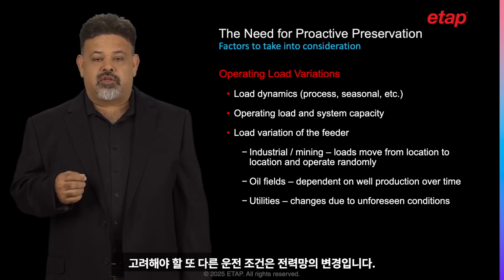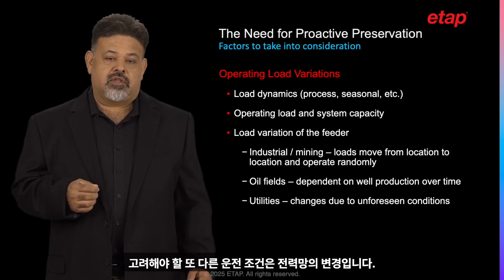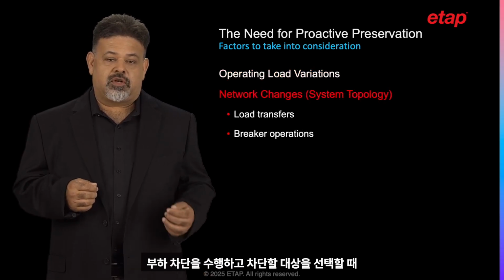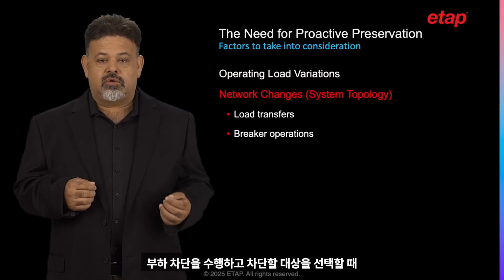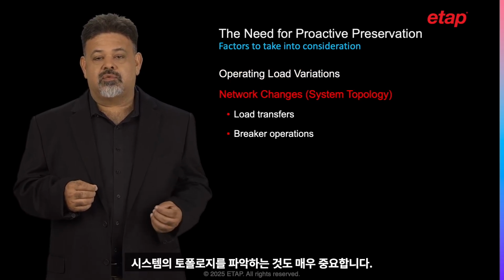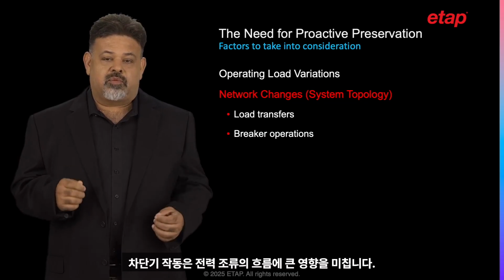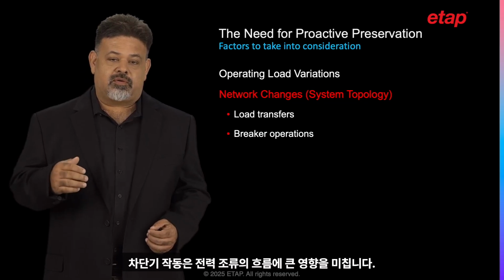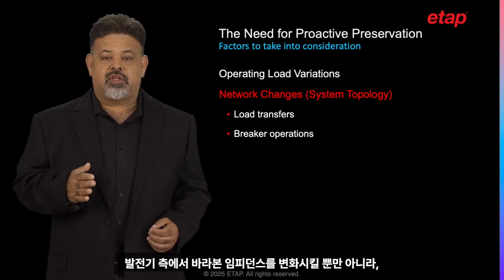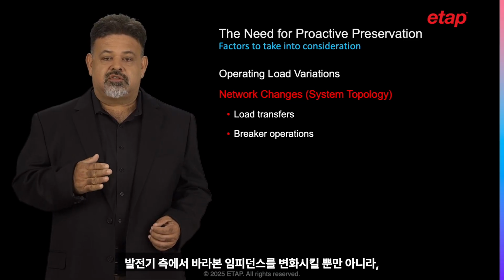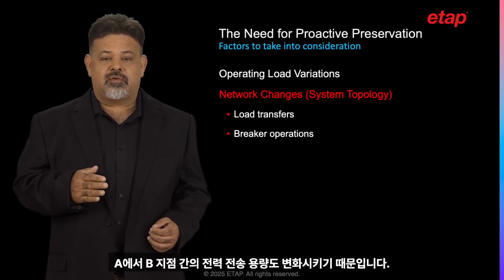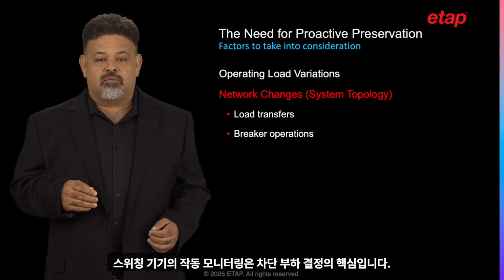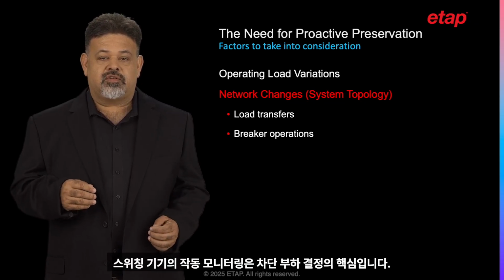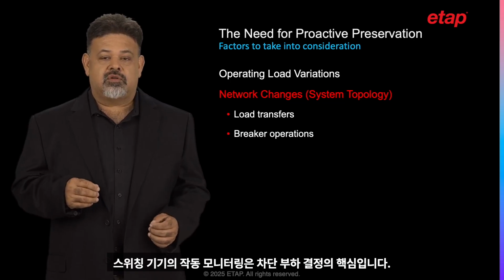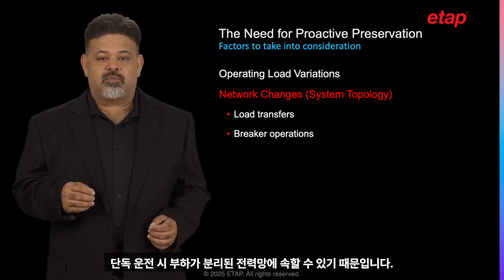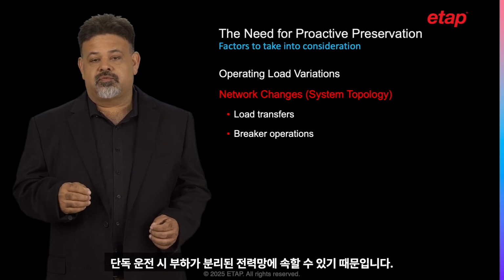Other system operating conditions to consider are network changes. The system topology is also important to know when performing load shedding and selecting which loads to drop. Breaker operations greatly affect the behavior of the power flows, as they change the impedance seen by the generators as well as the capacity of transferring power from point A to point B. Monitoring the operation of switching devices is a key factor for deciding which loads to drop, as they could be in a separate network if islanding occurs.